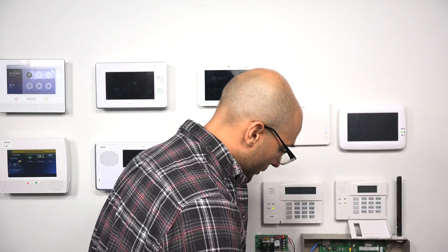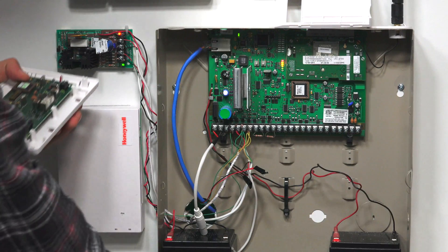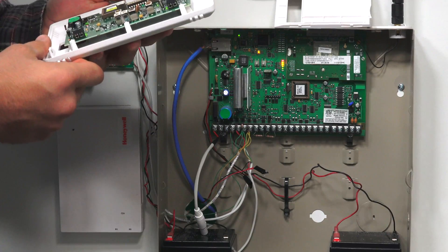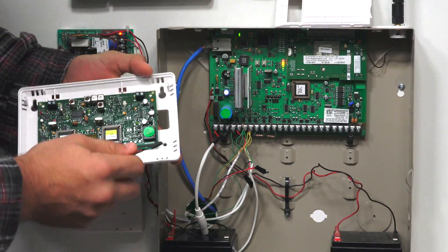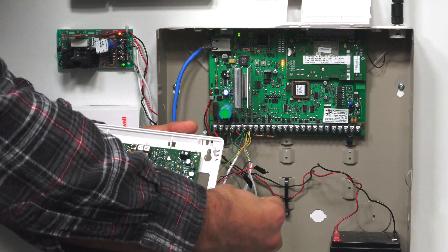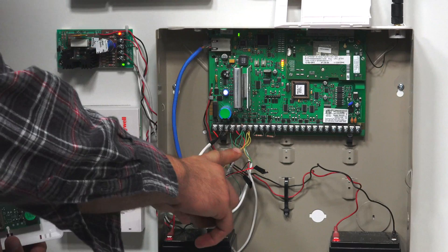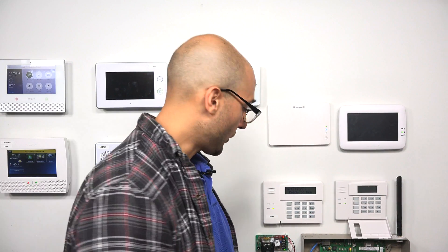If I open it up, you can see this connection here is for the mod plug — it plugs right in onto the board. This then connects back to the ECP bus on your system via these four terminals. It uses the same ECP bus that you use for any other device, such as a keypad or any other powered device that needs to pass data back and forth from the system.